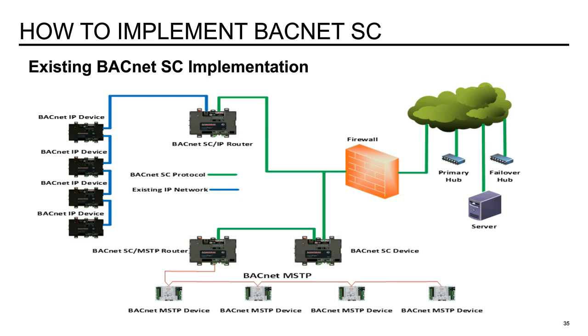So the server would be the server that is running, let's say, the building automation system. The hub is nothing more than, like I said, it could be a software device, it could be a hardware device, but basically it's a node, if you will, on the network that provides the encryption of the devices on the network between the hub and the devices that are downstream of the hub, and then for the server to communicate with. So in the case of a building automation system, the server would be the device that's hosting the building automation system's database, graphics, and things like that. And then the server is going to connect to the devices that are on the network through the hub.